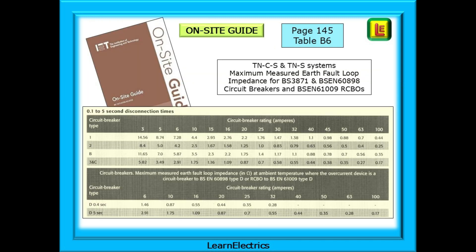If you have the On-Site Guide or OSG, you'll find Table B6 on page 145. Again, this contains data for TNCS and TNS systems and gives the maximum measured earth fault loop impedance for BS3871 and BSEN60898 circuit breakers and BSEN61009 RCBOs for different types.